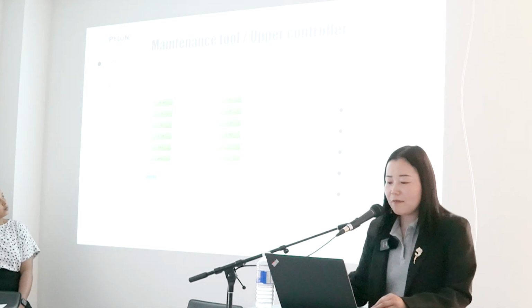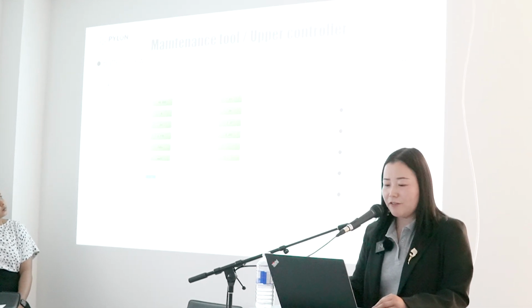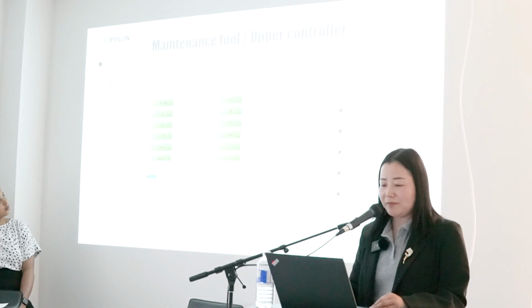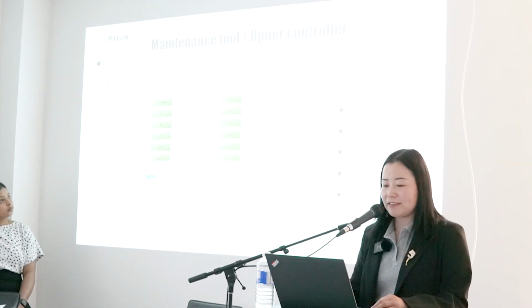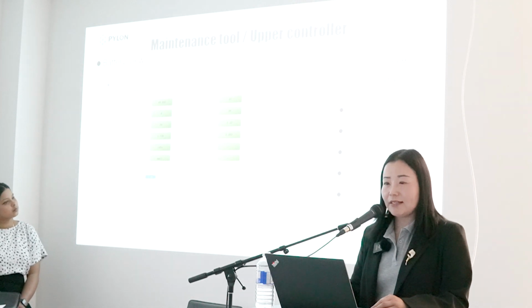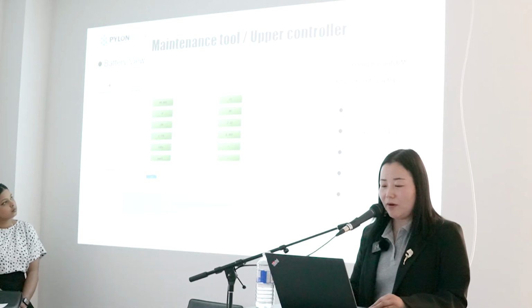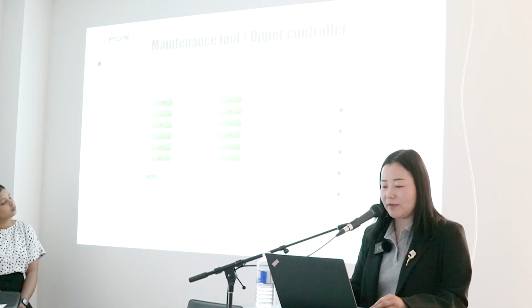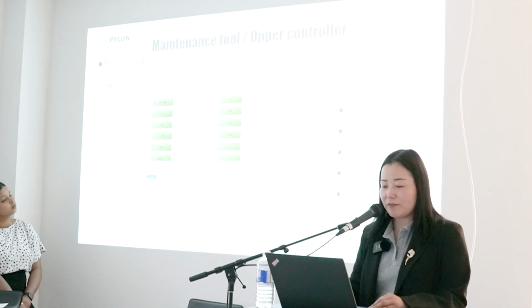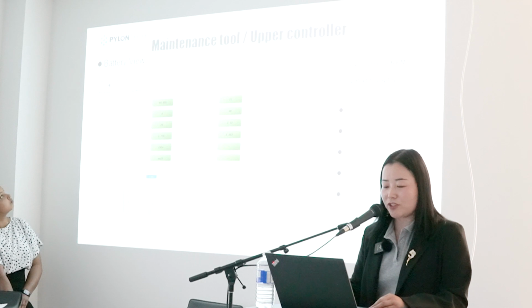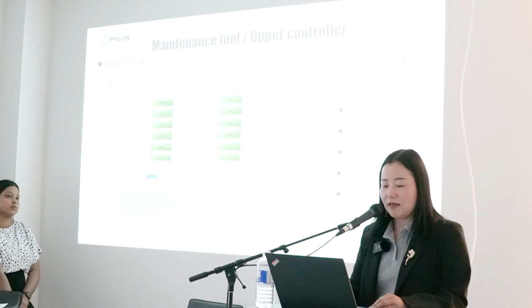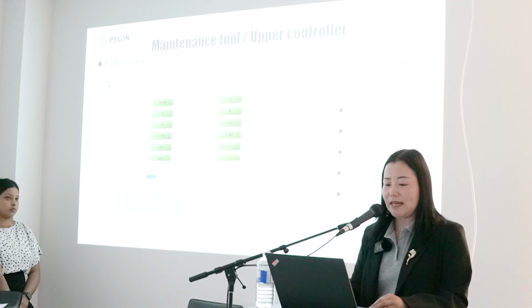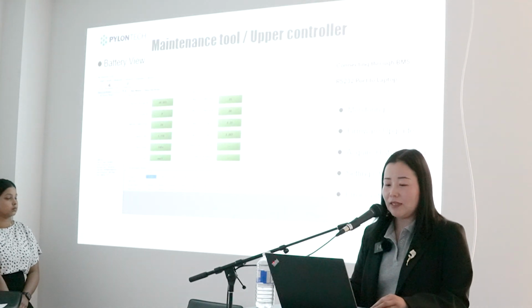On the main screen of BatteryView, the left table shows the battery type, software version, manufacturing date, serial number, and cell number, and the left green table shows basic information of voltage, current, capacity, status, and SOC. The right green table shows the cell temperature, voltage, and charge and discharge current, and there is also a cell information window including voltage and temperature. And the right one is the alarm information. If there are any problems, there is a red alarm symbol.